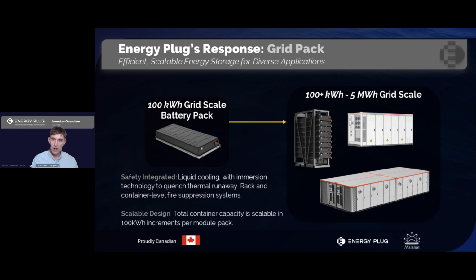So here we are also looking to bring in a 100 kilowatt hour battery pack. This is a more traditional liquid cooled one. The other battery we have is air cooled; this is a liquid cooled immersion technology. Basically, this will lead to a 20-foot container that is a 5 megawatt hour system in density, very, very similar to what we're seeing in the market.